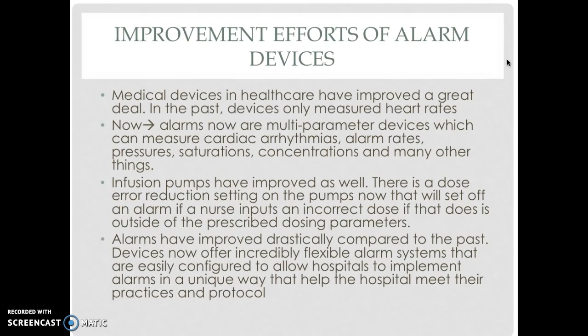Infusion pumps have improved as well. There is a dose error reduction setting on the pumps now that will set off an alarm if a nurse inputs an incorrect dose, if that dose is outside of the prescribed dosing parameters. Alarms have improved drastically compared to the past. Devices now offer incredibly flexible alarm systems that are easily configured to allow hospitals to implement alarms in a unique way that helps shape the hospital's practices and protocols.